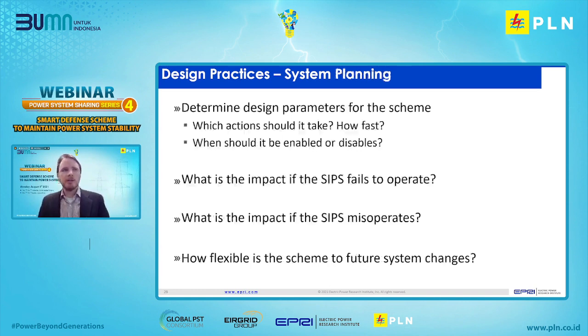Moving to the next slide. As part of the planning process, it's very important to determine the design parameters for the scheme. What actions should it take? How quickly? When should it be enabled and disabled? Perform the necessary transient stability studies, as well as load flow and protection studies to ensure that there is no interaction between different SPS schemes on the grid, like what happened in Norway.